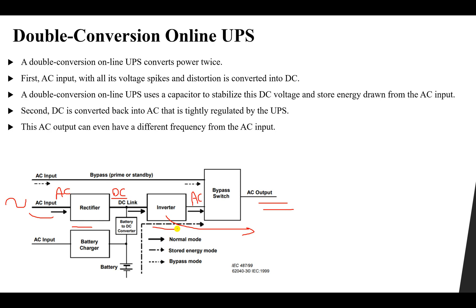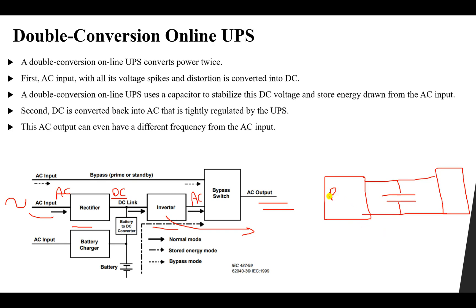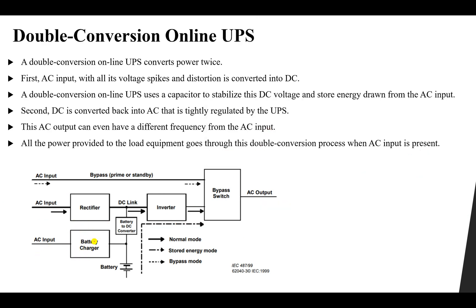You will see this configuration a lot in electrical power systems — it is called the back-to-back converters. A rectifier is connected to a DC link, and that DC link is connected to an inverter. This same configuration is used in the UPS. All the power provided to the load equipment goes through this double conversion process when we have an AC input.